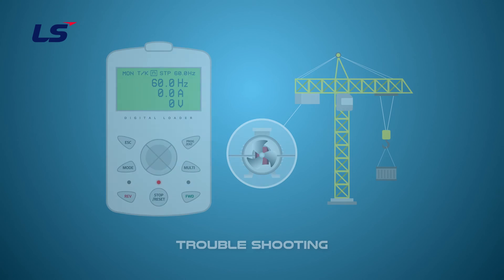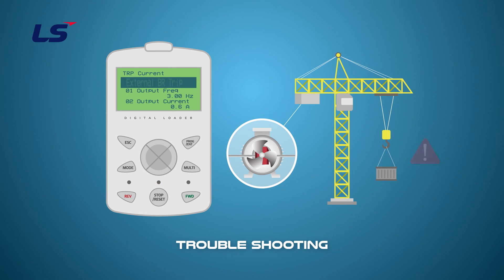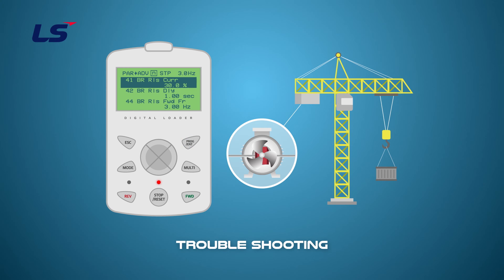If the open current or output frequency is not reached and stays for more than 10 seconds, external brake trip will occur. In this case, lower the percent value of the output current setting so that the drive output current value will be satisfied.